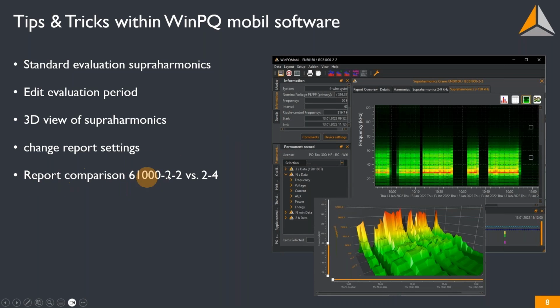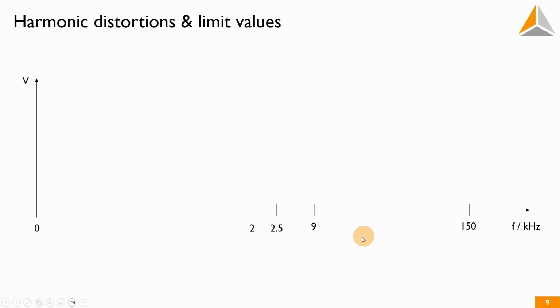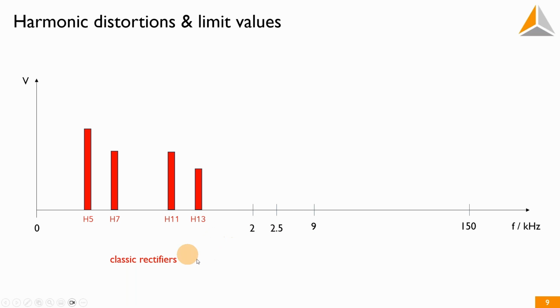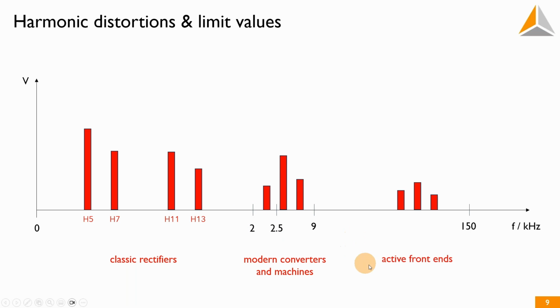So my comparison between 2-2 and 2-4 I explained, and one more slide just to get a better impression. This horizontal line represents our frequency in kilohertz, and we have classic rectifiers, the older ones, like a B6 bridge rectifier, which causes the 5th and 7th harmonics, 11, 13, and so on and so on. Modern converters and machines cause trouble within that range, and higher frequencies are often caused by, for example, active front ends.